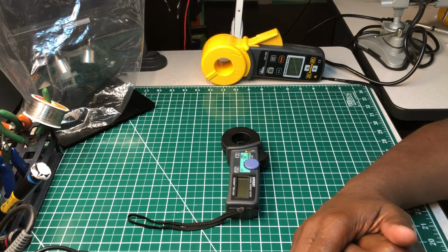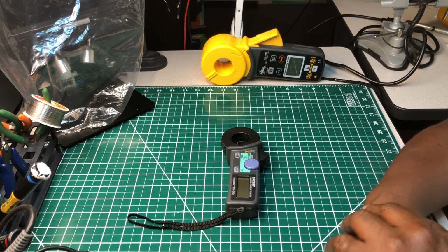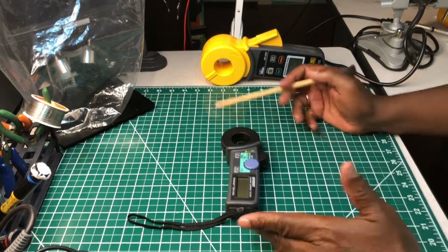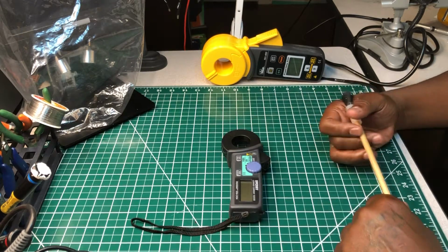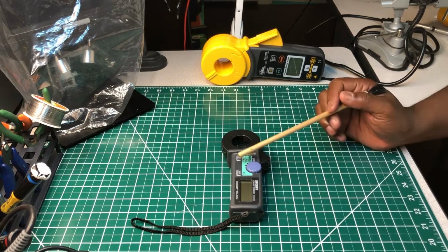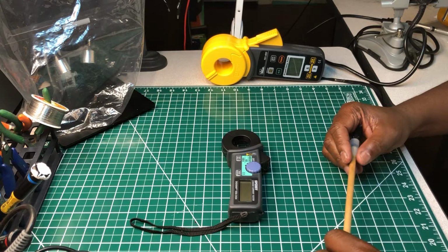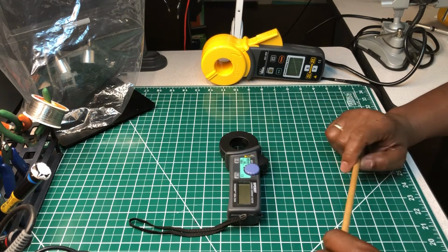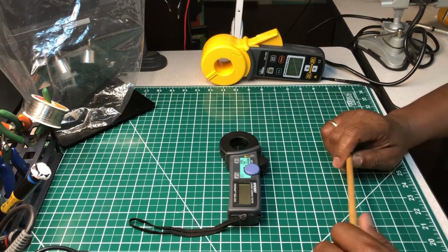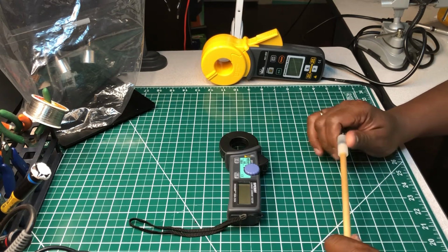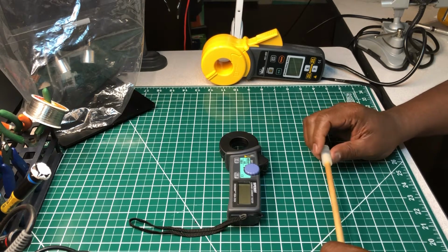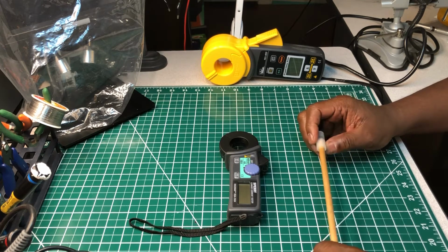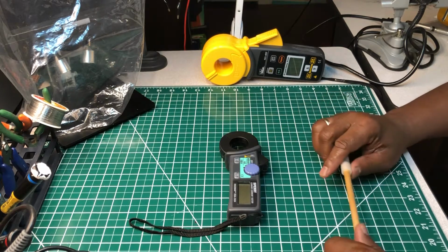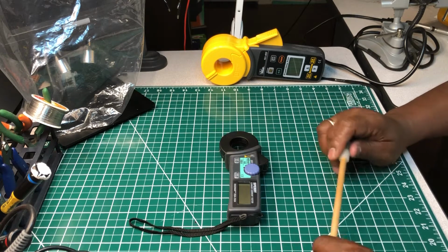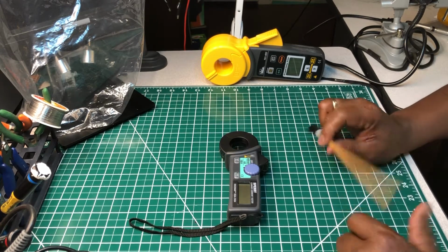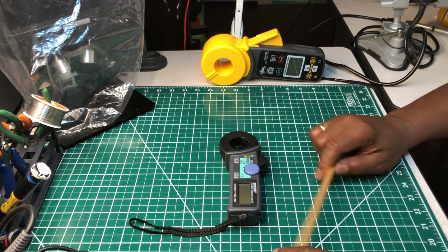This is part 2, and tonight I'm just going to show you what it can do. This test instrument is small in size but very important. I think every electrician should have one of these, maybe not this brand, but one of these test instruments, because you need it to measure milliamps and leakage current. You cannot measure leakage current with an ordinary clamp meter because it won't go that low, like 5 milliamps. This one will go lower than 5 milliamps, up to 399, up to 400 milliamps. This is a very special instrument.